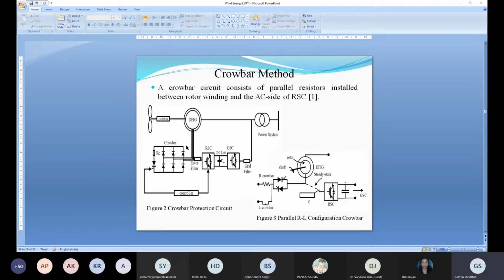So in a crowbar circuit, we connect a resistor through a diode rectifier and SCR. Under normal operation, the crowbar circuit is disconnected. When there is an overcurrent, the controller gets the signal and switches on the SCR, and the rotor is connected through the diode, crowbar circuit and SCR back to the rotor. At this time, the rotor side converter is disconnected from the DFIG, and the DFIG acts as an induction generator and takes reactive power from the supply. So the current will be controlled.